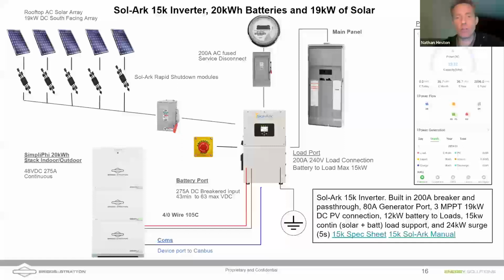And if you're really looking at backing up 400 amps worth of service and those 400 amps are justified, then I would recommend more than one Sol-Ark inverter, right? Each inverter is capable of 12 kilowatts of output power from the loads, which, if I do my math correctly, I believe is about 60 amps on the AC side of things. So if you're really trying to back up 400 amp service, I would recommend using parallel 12K or 15K Sol-Arks. You can parallel up to 12 of these inverters to cover that.